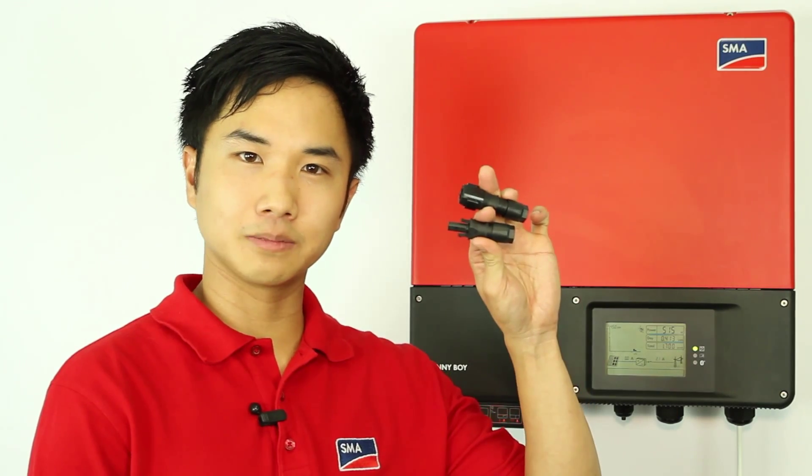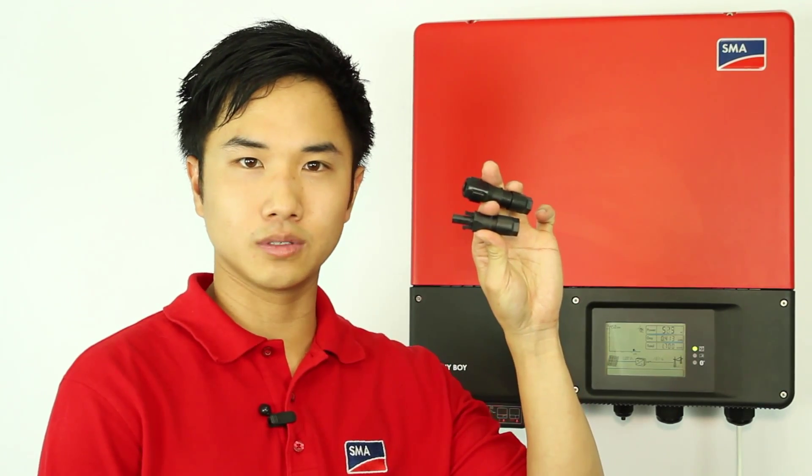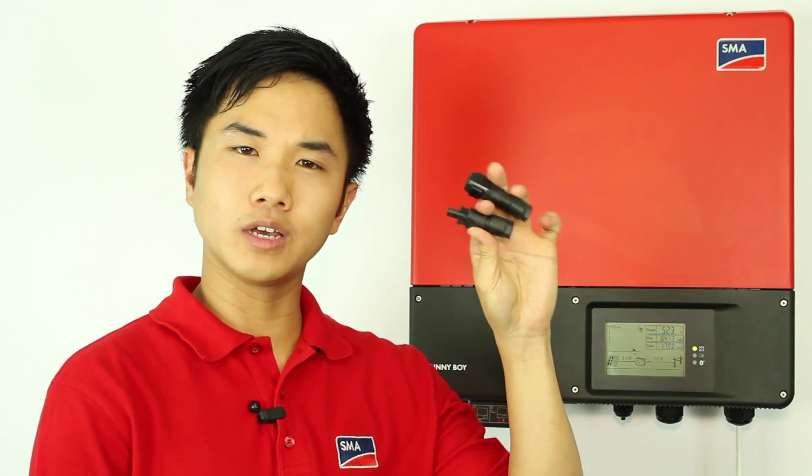SMA has designed SUNCLIX plugs that are very easy for installers to use. According to the installation manual, all unused SUNCLIX terminals must be sealed with the SUNCLIX plugs in order to have the IP65 rating, or else the connection area is only IP54.